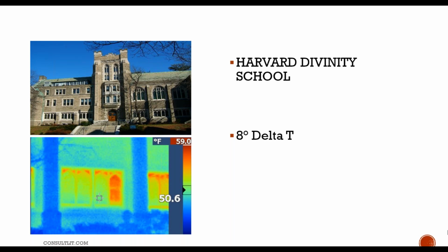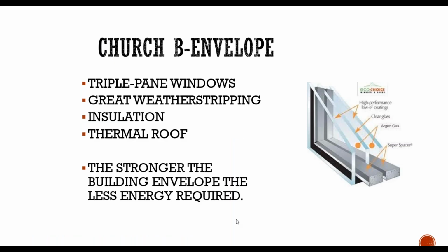So just by adding a storm window to a single pane window, we're retaining 8 degrees more than where we're not. Correct. The building is maintaining 8 degrees more, because you can see the heat escaping where it was compromised. It was obviously colder, so they were trying to maintain a 68-degree indoor temperature, but a single pane window compromises the envelope, and the heat moves out accordingly. Okay, great.